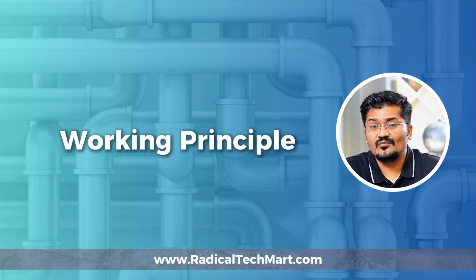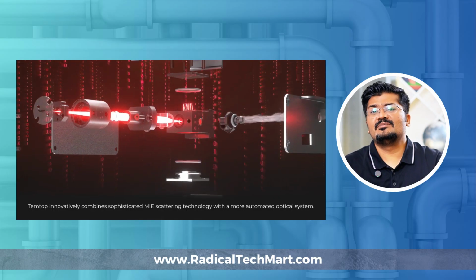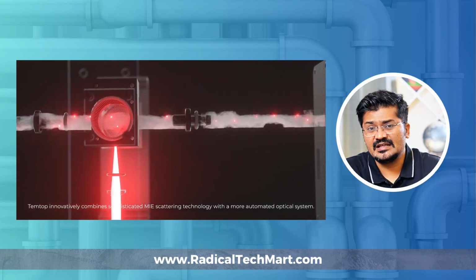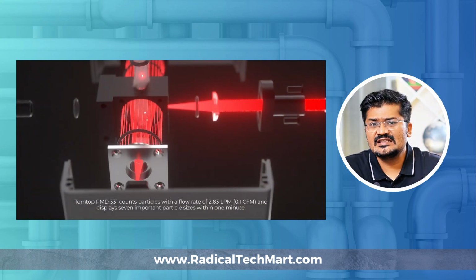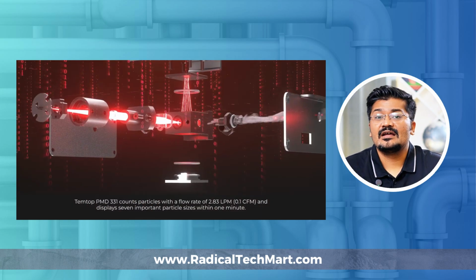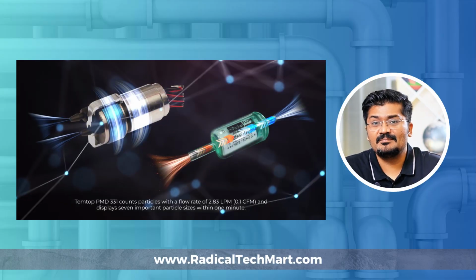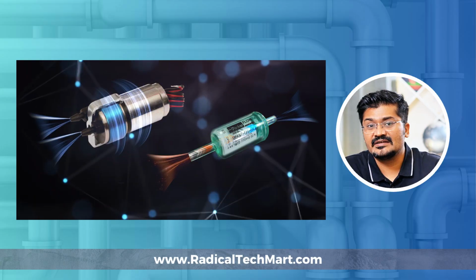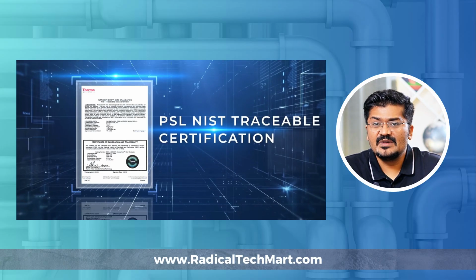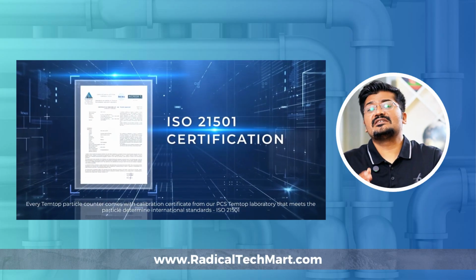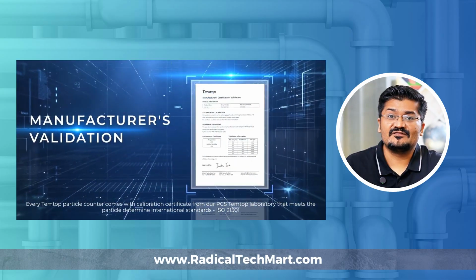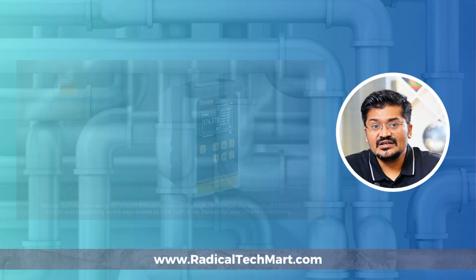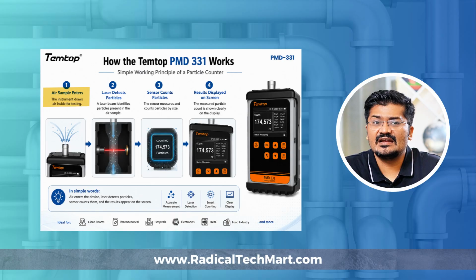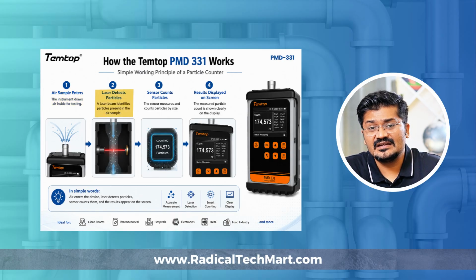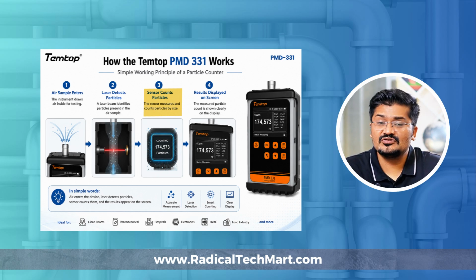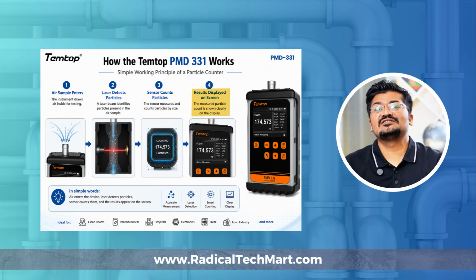Now, let's understand the working principle of this instrument. Temtop PMD 331 works on the light scattering technique. Inside the instrument, air is pulled through the sensor with the help of an internal pump. When air passes through the laser light path, the particles present in the air scatter the light. The sensor detects this scattered light. Based on the scattered light signal, the instrument calculates the particle count and classifies it according to particle size. So, in simple words, the instrument takes an air sample. Then laser light detects particles. Then the sensor counts the particles. And finally, the result is displayed on the screen.